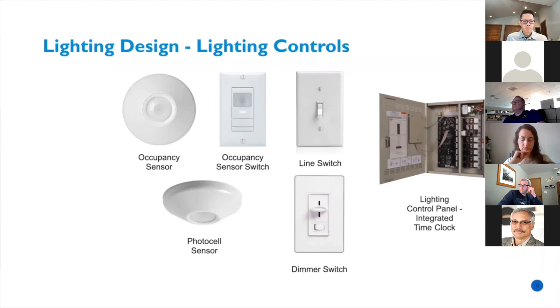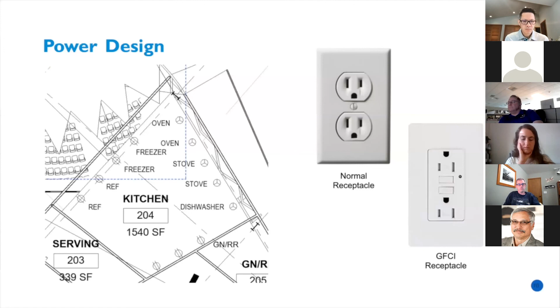output accordingly. When creating the power design for the kitchen, we included electrical connections for the ovens, stoves, and dishwasher. These are large equipment that take up a lot of load, about 1200 to 1500 volt amps each. The refrigerators and freezers will be powered via a receptacle with a dedicated circuit for each. There are convenience outlets on the side of the kitchen. We will have a few ground fault circuit interrupter receptacles in the kitchen space. GFCI receptacles have an internal breaker in them that trips when it senses a ground fault. These are usually found near sinks or where there is water nearby.